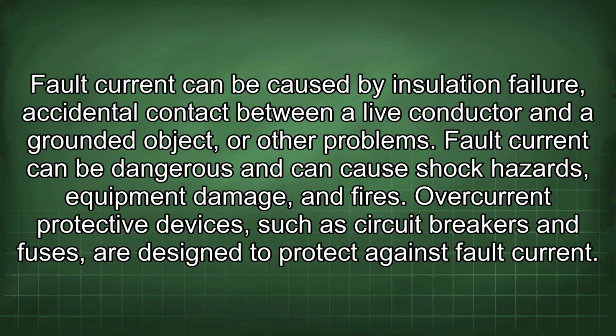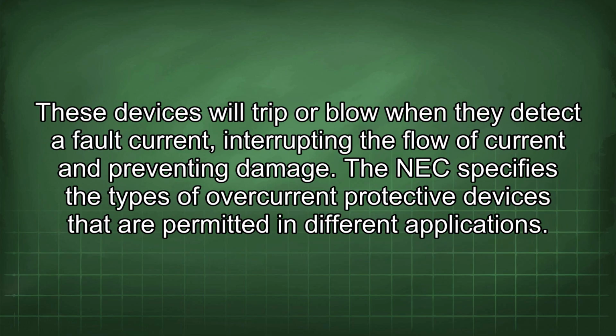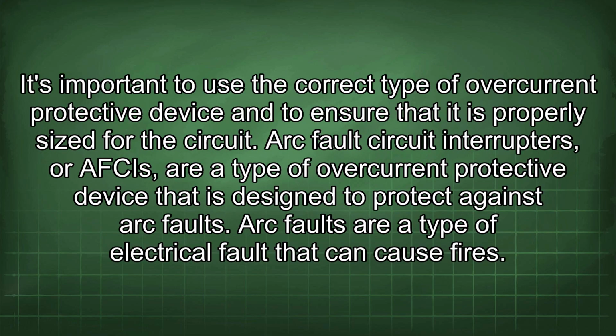Overcurrent protective devices, such as circuit breakers and fuses, are designed to protect against fault current. These devices will trip or blow when they detect a fault current, interrupting the flow of current and preventing damage. The NEC specifies the types of overcurrent protective devices that are permitted in different applications. It's important to use the correct type of overcurrent protective device and to ensure that it is properly sized for the circuit.